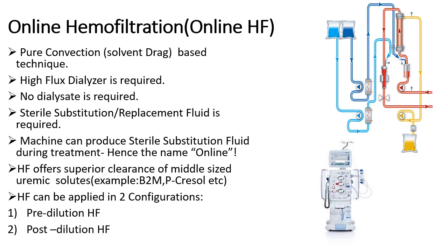In terms of clearance, online HF can remove medium to large sized uremic solutes such as beta-2 microglobulin. Haemofiltration can be applied in two configurations: pre-dilution haemofiltration, where the substitution fluid is administered just before the filter, and post-dilution haemofiltration, where the substitution fluid is administered after the filter.